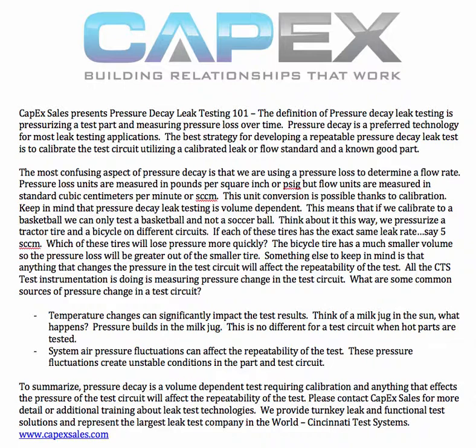So what are some of the common issues that cause the pressure change or cause repeatability issues in pressure decay leak testing? The number one, without a doubt, is temperature. Temperature changes can significantly impact the test results.